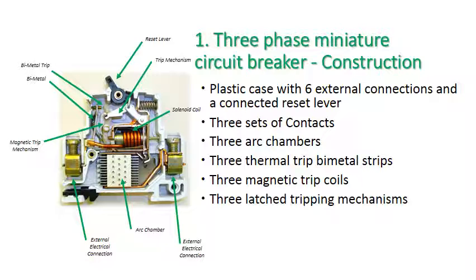This is obviously a single-phase circuit breaker. A three-phase miniature circuit breaker has three sets of what you see here, side by side, connected together. As a result, it has a base with six external connections and a reset lever that's joined across all three. There's obviously three sets of contacts, three arc chambers, three thermal bimetal strips, three magnetic trip coils, and last but not least, three latch tripping mechanisms.